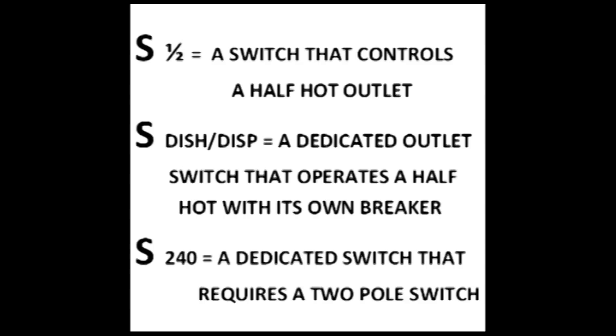Switch dish disposal—that is a half hot switch that powers a dishwasher disposal circuit and also has the potential of 240 volts. Switch 240—that could indicate many things, but it means it's a two-pole switch. It's for perhaps a wall heater, heat lamps, or some other device that requires 240 volts.